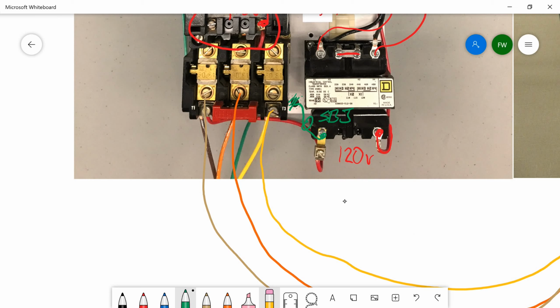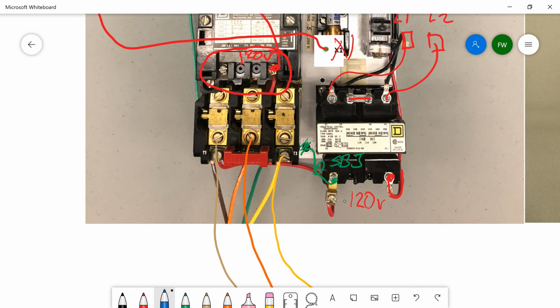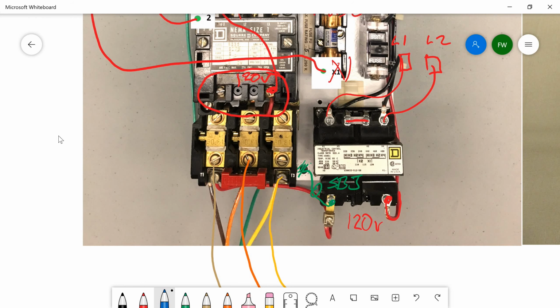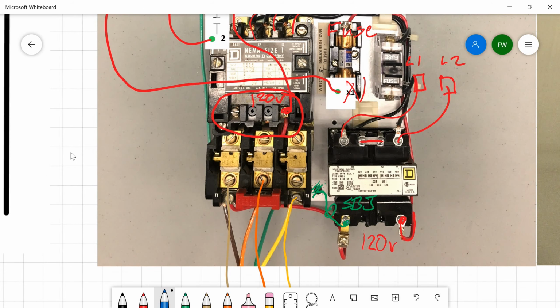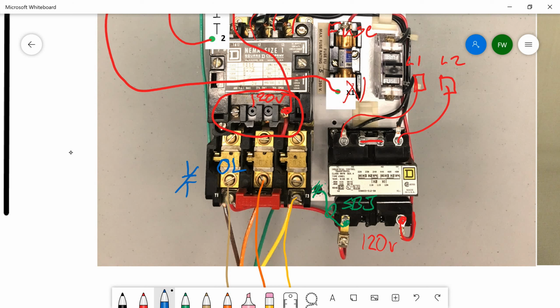Okay, so now we're going to represent the neutral with a blue wire. So let's complete our neutral. Over here, we're going to have a contact at the bottom of our overloads that's going to be held closed. So these are our overloads right here. And we're going to come out of our control transformer, and we're going to take it to one side of our overload, normally open, held closed terminal. And then on the other side of that terminal, typically it's jumpered for you, but always double check. You have to take it to the other side of the coil.